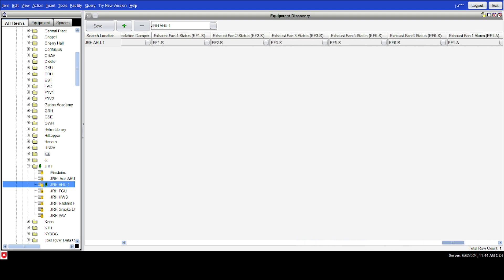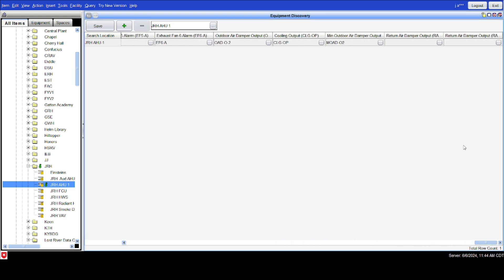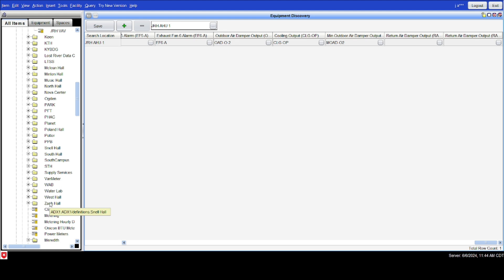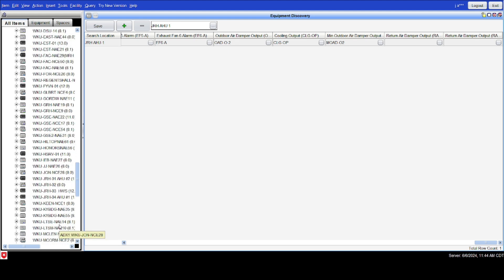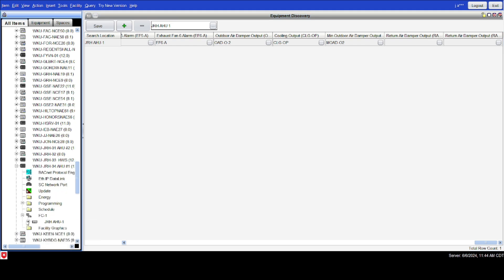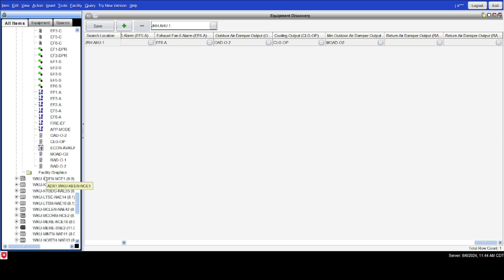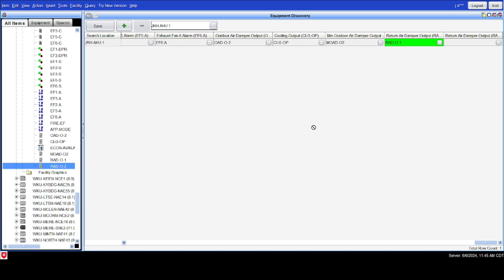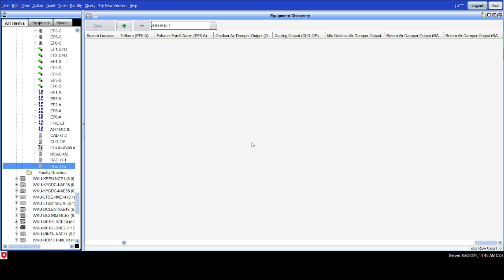I've deleted that extra equipment object, and now I'm scrolling over to the original equipment object. Here are my two empty points that are in the original equipment object — that's what I want to use. By doing what you saw me do before, it modified the equipment definition in such a way that I have those points available to add into the original equipment object. I know this is getting confusing, but you really have to spend the time to understand how equipment definitions and equipment objects work. I'm simply going to drag them and drop them into place, then save.